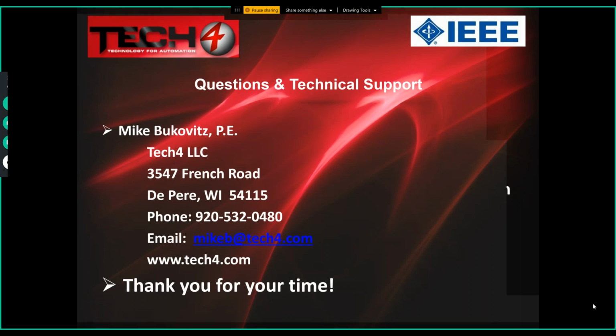Any other questions, gentlemen? Mike, one thing I wanted to mention is your drawings when you're showing the virtual main earlier in the conversation was showing two relays, one for the medium voltage side and one for the low voltage side. That can be done with one relay. Depending on the relay you have, that's absolutely true. That does not have to be two separate physical devices, depending on the relay that you have. Absolutely.